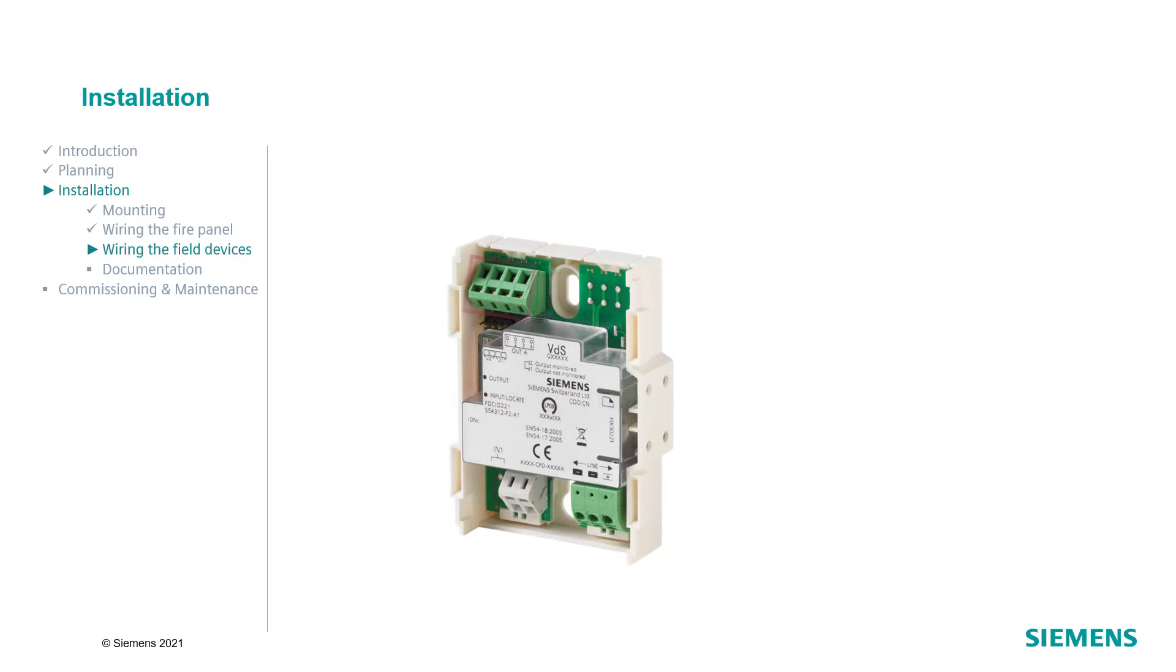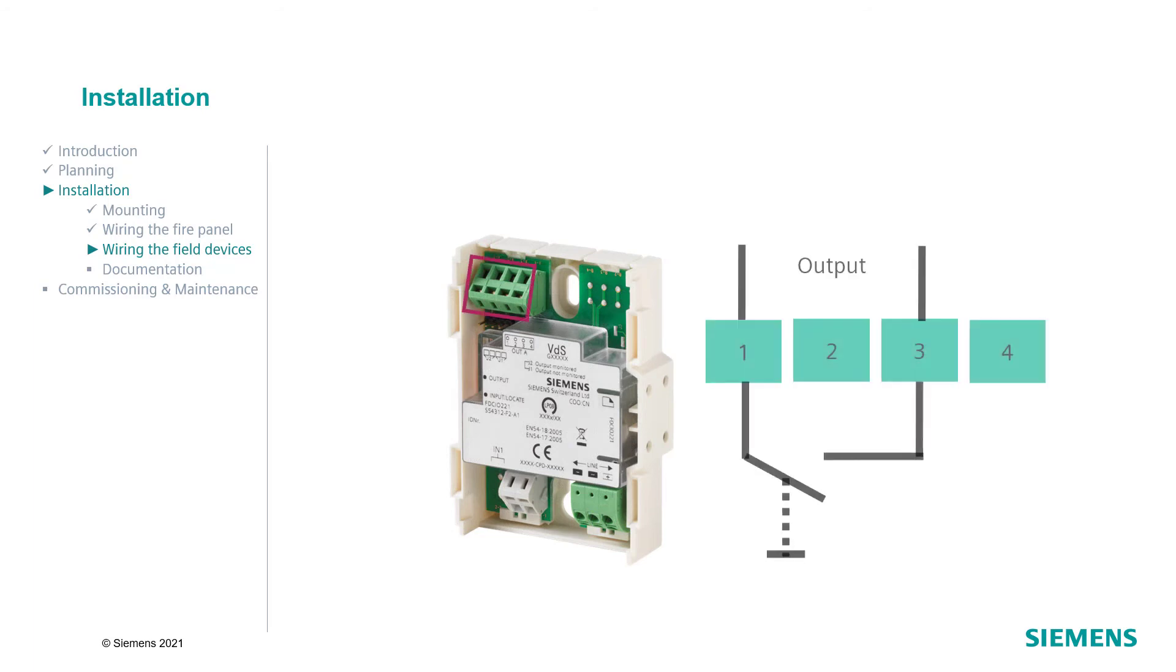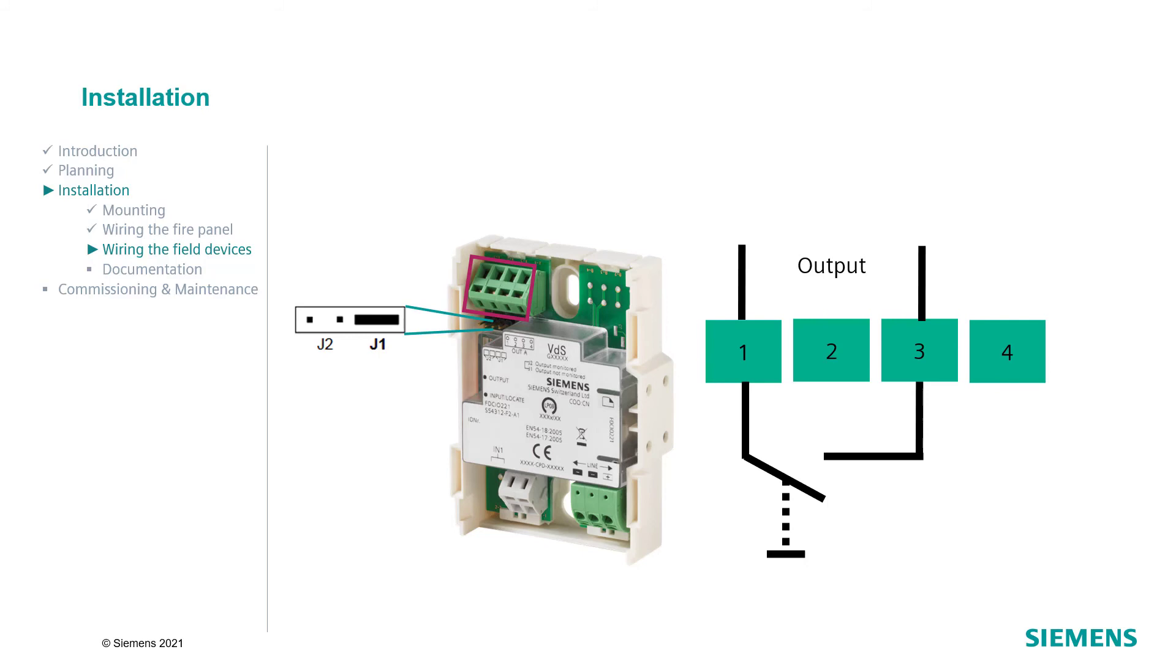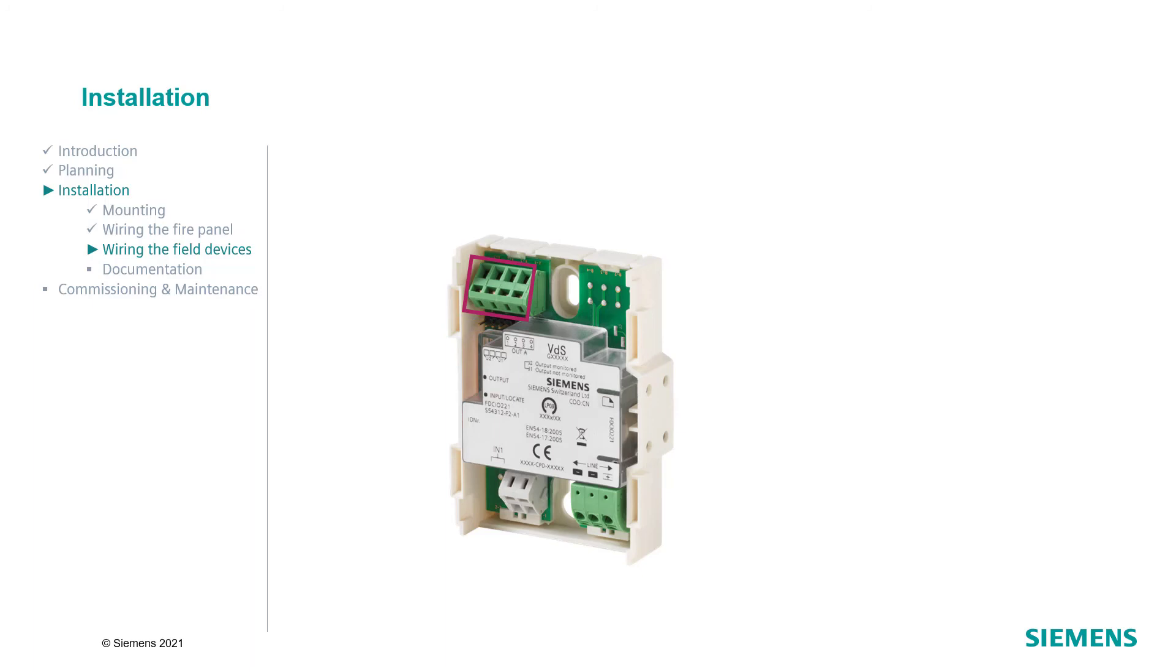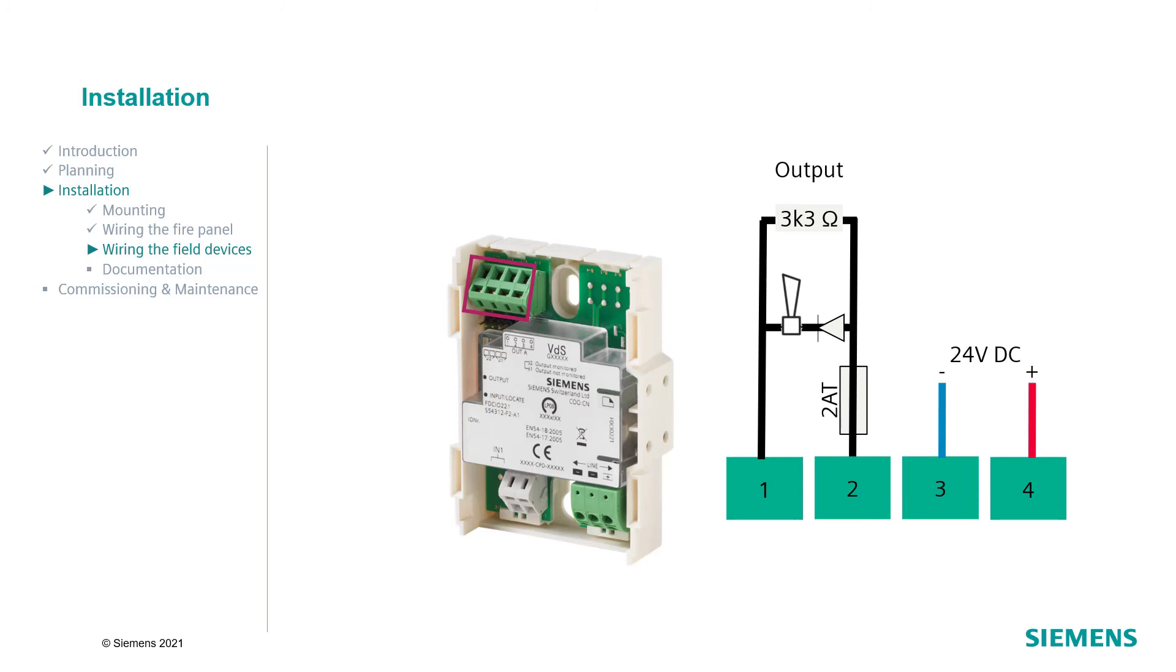The outputs of the FDCI221 and the FDCI361 can also be configured as potential free relay contacts. In this case, make sure that the jumper is plugged into J1. It can also be used as a monitored output. That means, the module switches the externally supplied DC24V voltage to the output when it becomes active. For this, make sure that the jumper is plugged into J2.